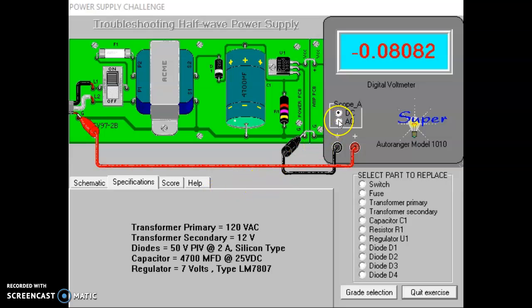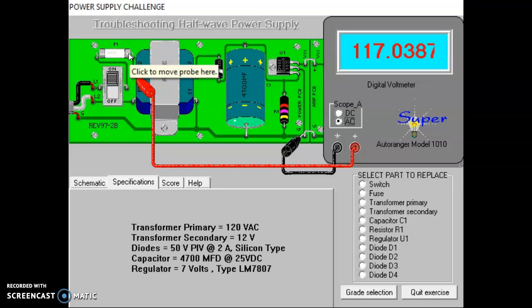So let's start out in a logical manner. We're going to start with the AC sense mode for our voltmeter, and I always start right at the primary coil. If I have an AC voltage, in this case we got 117, which is within our range of 110 to 125, we got a good AC voltage going in.